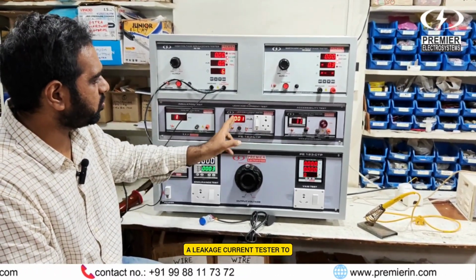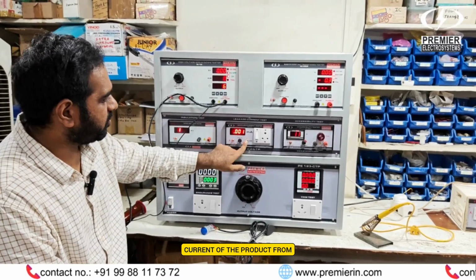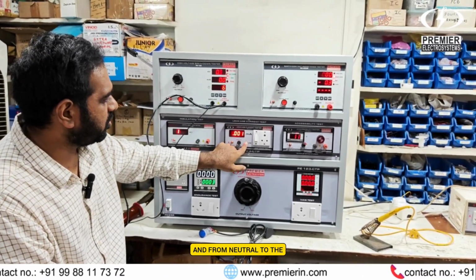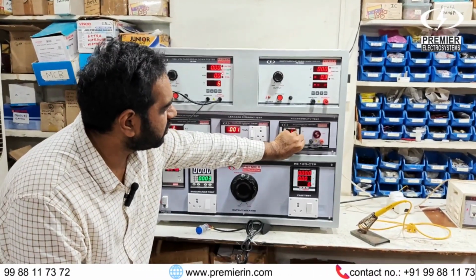This is a leakage current tester, used to test the leakage current of the product from line to body and from neutral to body. This is the accessibility tester with variable voltage.